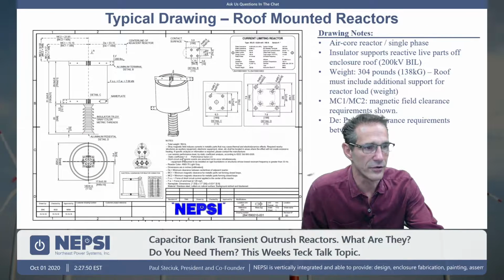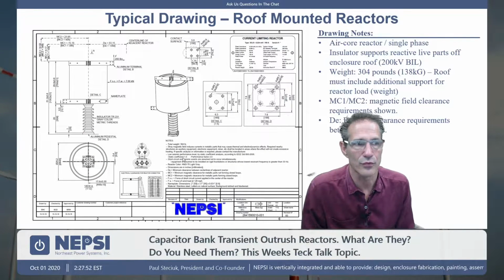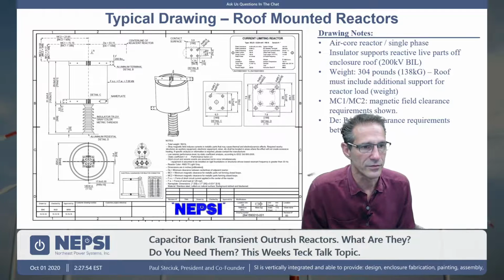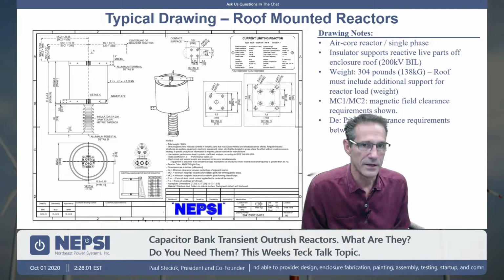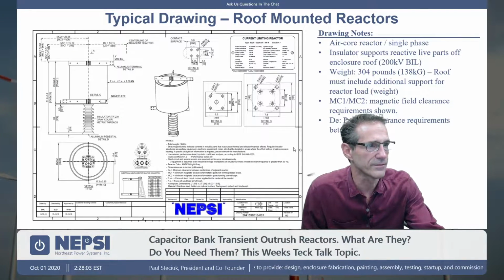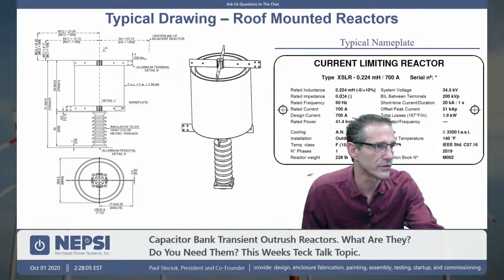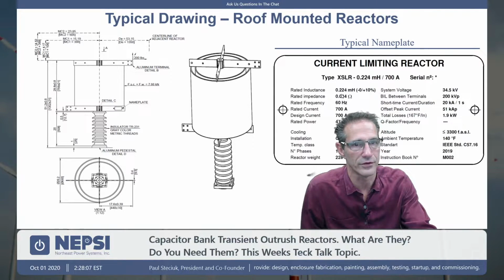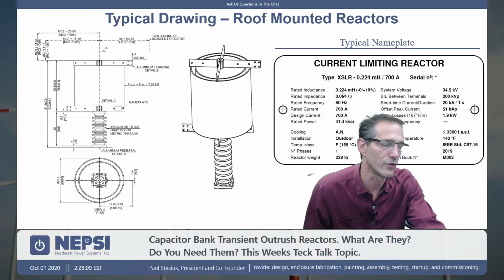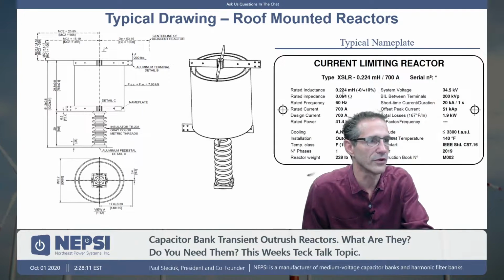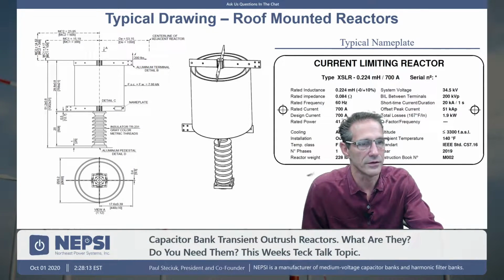So just kind of continue on. This is a typical outrush reactor. We just took some clips of a typical outrush reactor. It is much bigger than transient inrush reactors. And in this particular case, this outrush reactor is 0.224 millihenries, 224 microhenries, with a 700 amp rating associated with it.